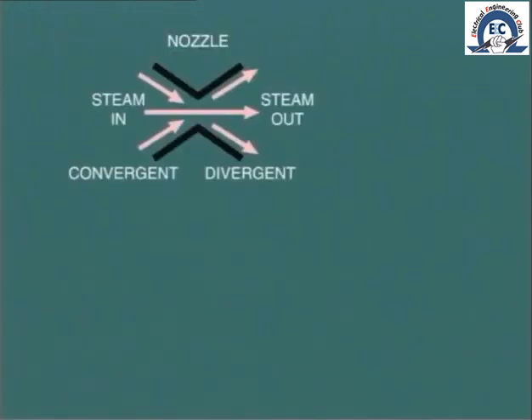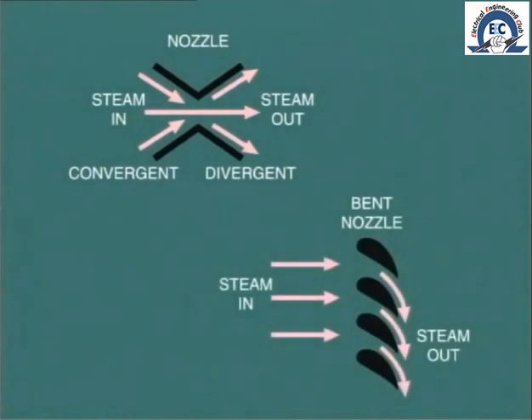Actually, each pair of stationary blades is shaped to form a convergent divergent nozzle. However, the form of the nozzle is bent to receive the steam exiting from the previous moving stage and then to turn and redirect the steam onto the next moving stage. Now, before you raise the question of impulse and reaction type blading, let me say that in practice, when you're operating a turbine, it's not vitally important whether the blading is impulse or reaction. This is really a design consideration.